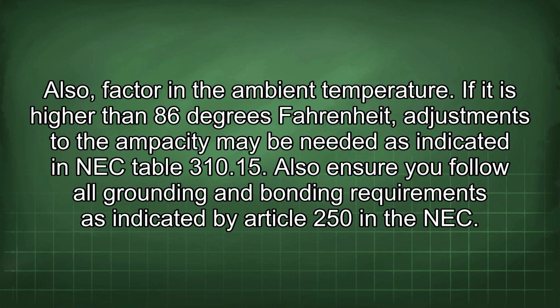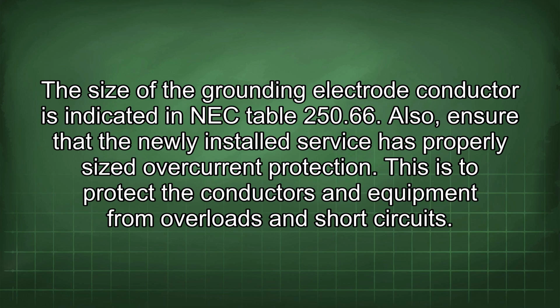Also, factor in the ambient temperature. If it is higher than 86 degrees Fahrenheit, adjustments to the ampacity may be needed as indicated in NEC Table 310.15. Also ensure you follow all grounding and bonding requirements as indicated by Article 250 in the NEC. The size of the grounding electrode conductor is indicated in NEC Table 250.66. Also, ensure that the newly installed service has properly sized overcurrent protection.